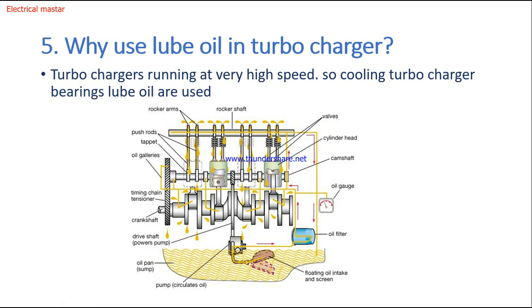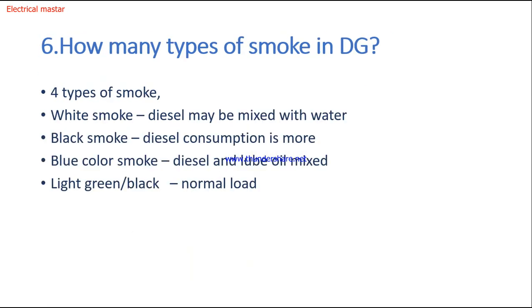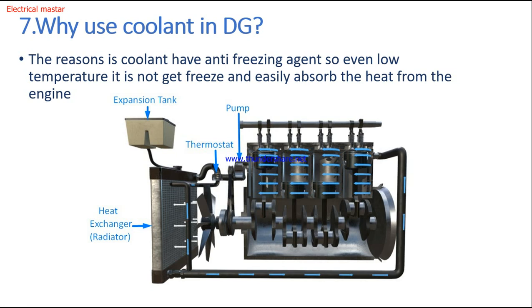Fifth question: why do we use lube oil in the turbocharger? The turbocharger fans run at very high RPM, so their temperature becomes very high. The bearings connected to these fans also produce a lot of heat, so we use lube oil to cool the turbocharger bearings. Sixth question: how many types of smoke are there in a diesel generator? There are four types: white smoke — diesel may be mixed with water; black smoke — diesel consumption is excessive; blue smoke — diesel and lube oil are mixed; light green or light black smoke means the generator is working under normal load.